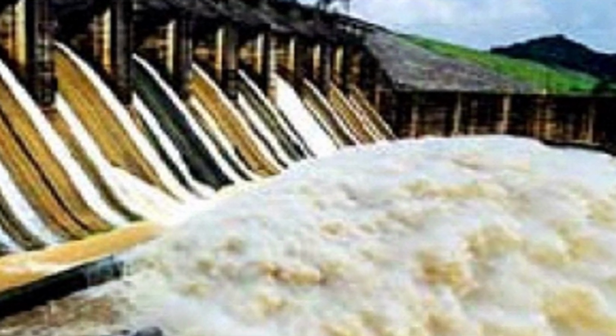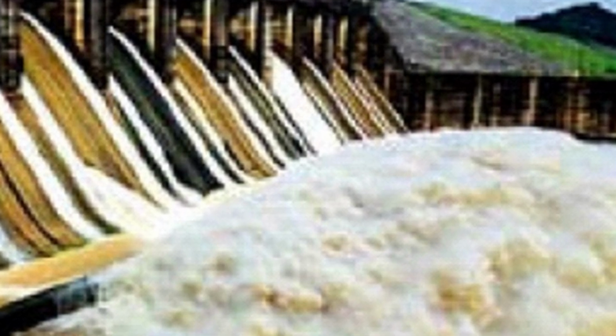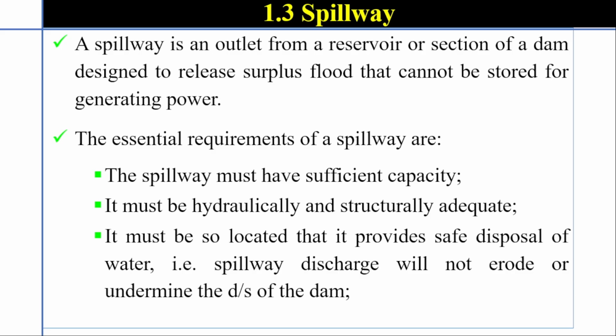This is the next topic: the spillway. A spillway is an outlet from a reservoir or section of a dam designed to release surplus flood that cannot be stored for generating power. The essential requirements of a spillway are: the spillway must have sufficient capacity. It must be hydraulically and structurally adequate. It must be so located that it provides safe disposal of water. That means spillway discharge will not erode or undermine the downstream of the dam.